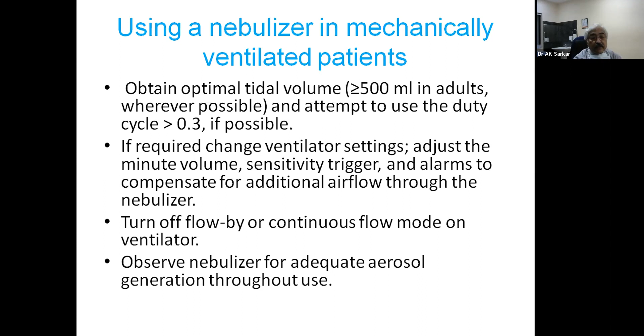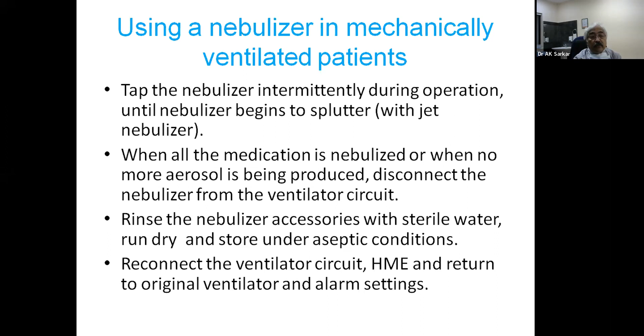When all the medication is nebulized, and no more aerosol is being generated, then disconnect the nebulizer from the ventilatory circuit. It is very important. Don't keep it with the circuit. And then rinse the nebulizer accessories with sterile water, then dry and store under aseptic conditions. And once you have done, you must reconnect the HME if you have taken it out. And if the ventilator was in support mode, then go back to the support mode, or whatever mode he had been in with that patient. And you need to adjust your alarm settings again.